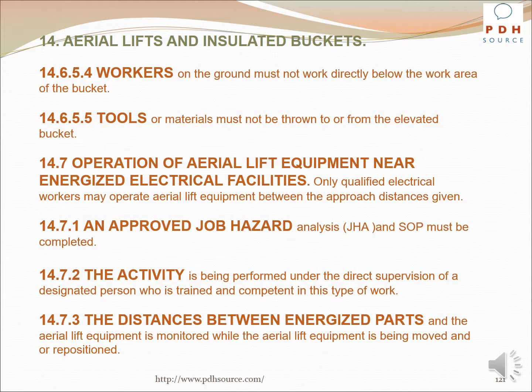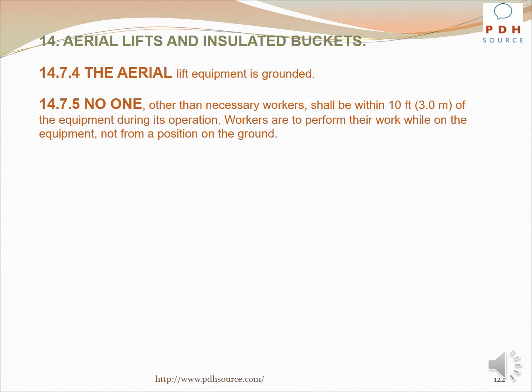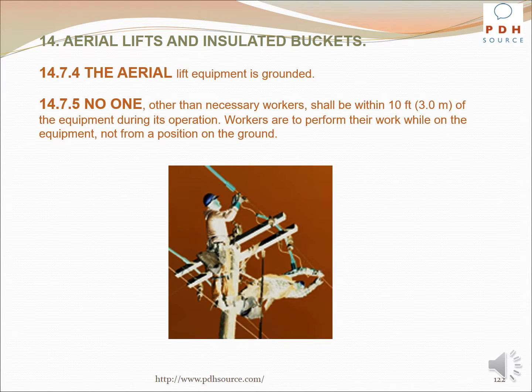An approved job hazard analysis must be completed. The activity is being performed under the direct supervision of a designated person who is trained and competent in the work. The distances between energized parts and the aerial lift equipment is monitored while the aerial lift equipment is being moved or repositioned. The aerial lift equipment is grounded. No one other than necessary workers shall be within 10 feet of the equipment during its operation. Workers are to perform their work while on the equipment, not from a position on the ground.